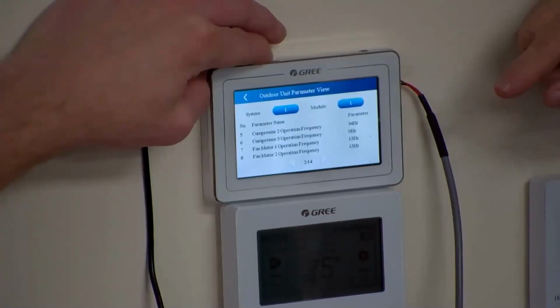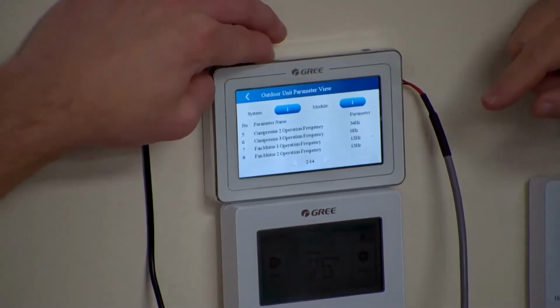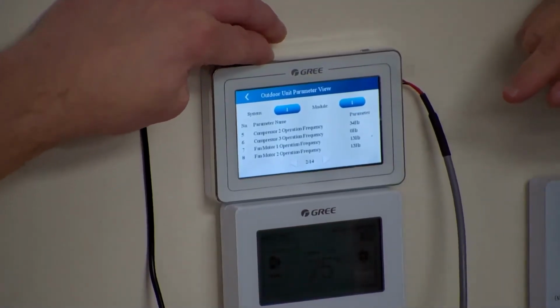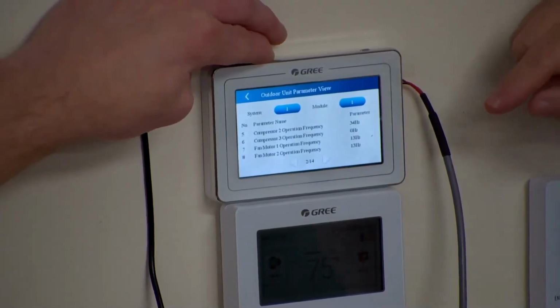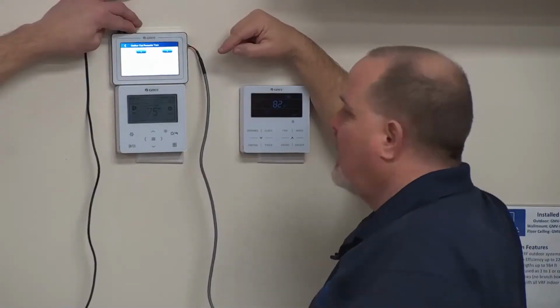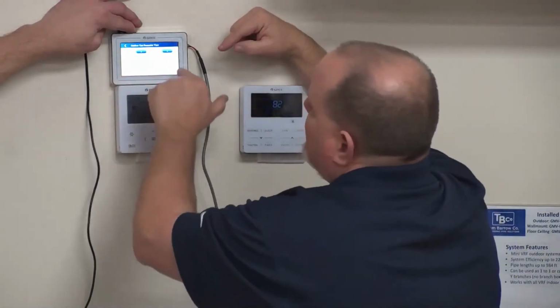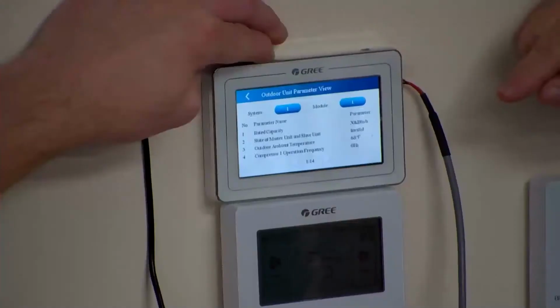Well, to me, I've got a 10-degree demand, right? My fan motors are only at 13 hertz. My compressor's only at 34 hertz. Why? Well, I'll tell you why. Because the outdoor temperature is 68 degrees.